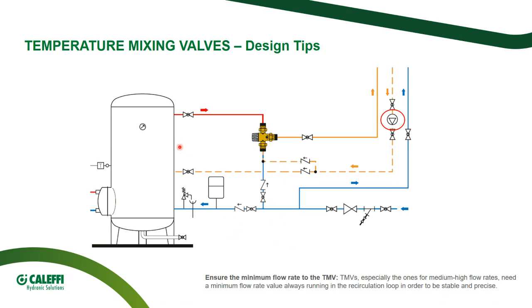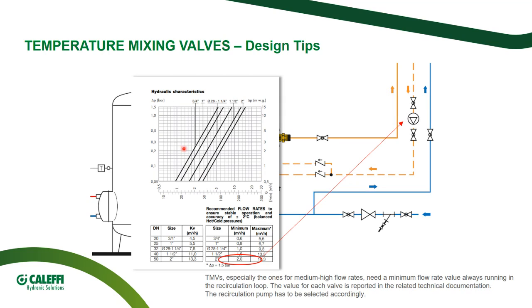comfort. Another tip, as we said before, these kinds of valves always need a minimum recirculating flow rate. So the technical data sheet of any mixing valve reports the minimum flow rate to ensure stable operation. So take this data into account when you size and when you choose the recirculating pumps.